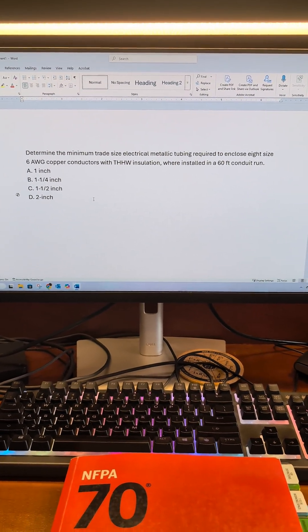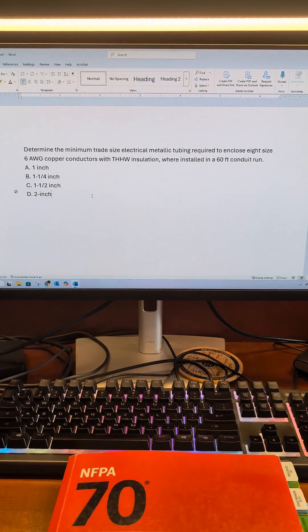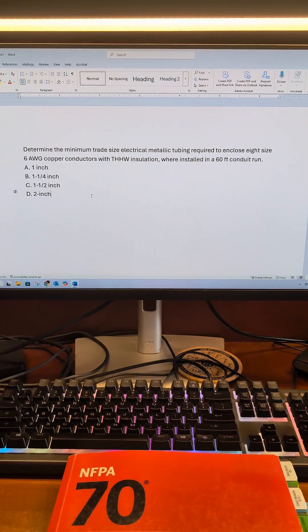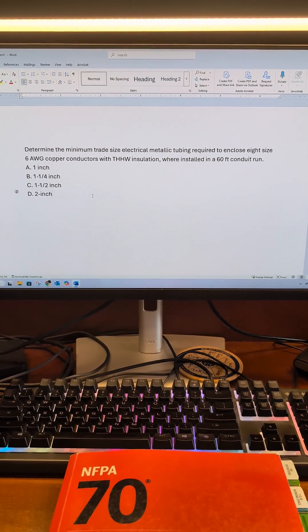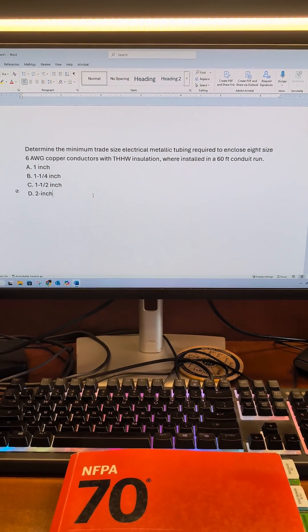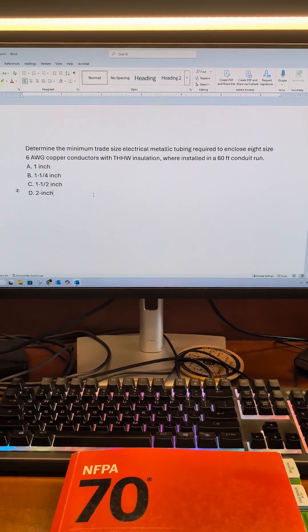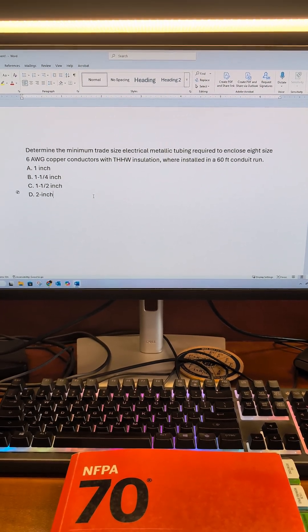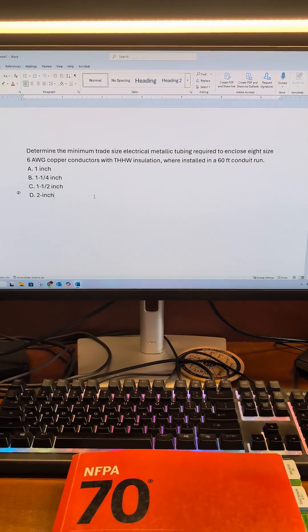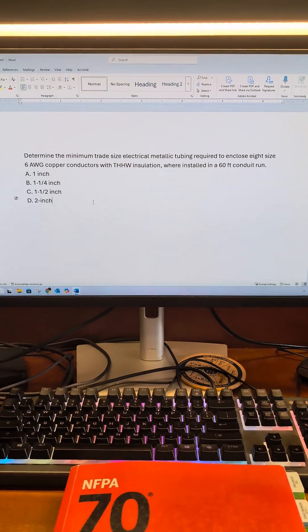Determine the minimum trade size electrical metallic tubing required to enclose eight size number six American wire gauge copper conductors with THHW insulation, installed in a 60-foot conduit run.